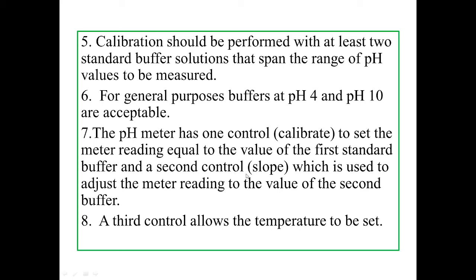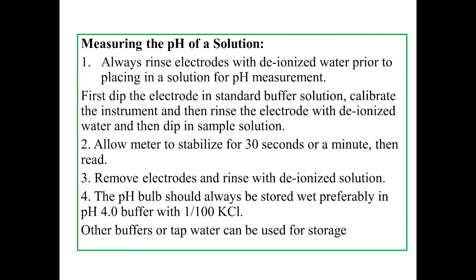Using the second control button, which is usually called slope, adjust the reading of the second buffer. What was the reading of the second buffer? Say 10. So adjust the reading to 10. Now your instrument is calibrated. The third control button is used to set the temperature depending upon the temperature of the solution whose pH is to be determined.